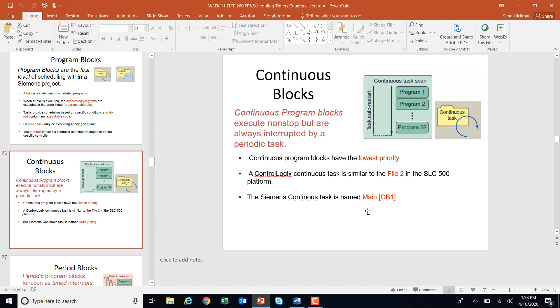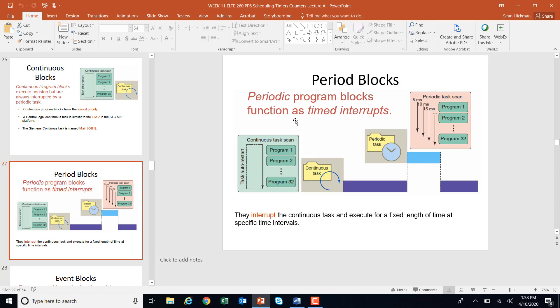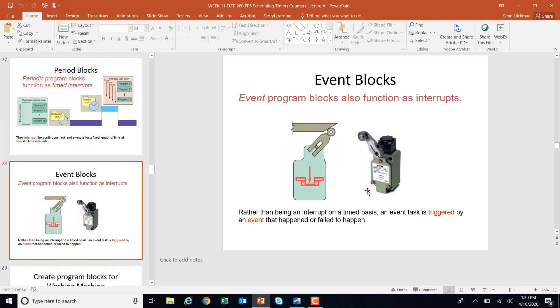In a periodic block we might have a timed interrupt — for example, every one second we might check for an error. When a periodic task runs, it stops the main OB, runs the periodic task, and immediately goes back to the main OB. The main OB has the lowest priority; the periodic task has much higher priority. We could also have an event interrupt — if something hits a limit switch, it calls an event block, stops everything, runs only the event block, then returns to the main program. So these are different levels of scheduling.